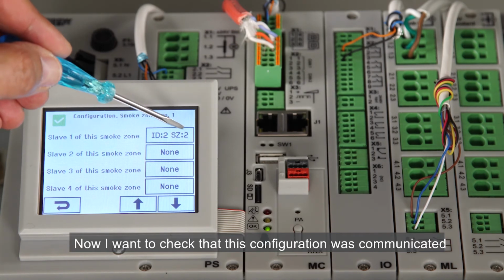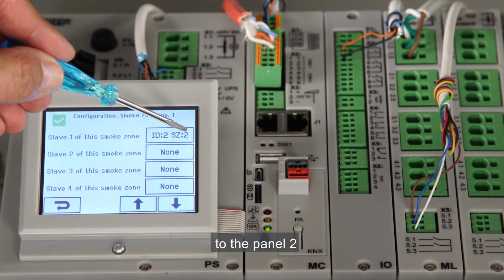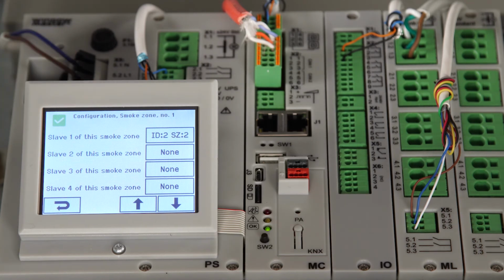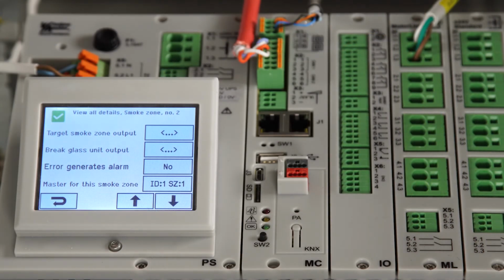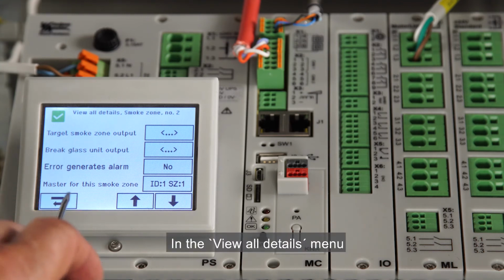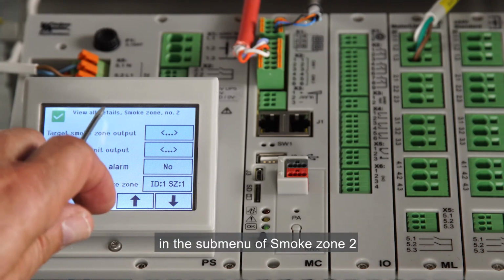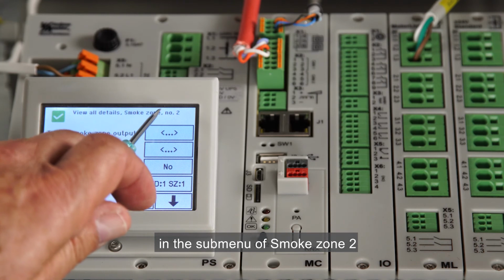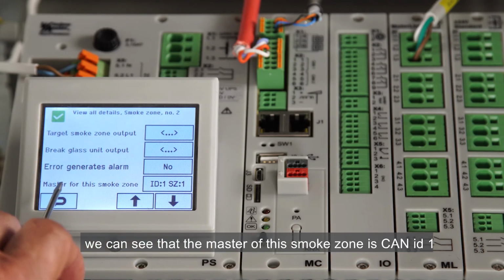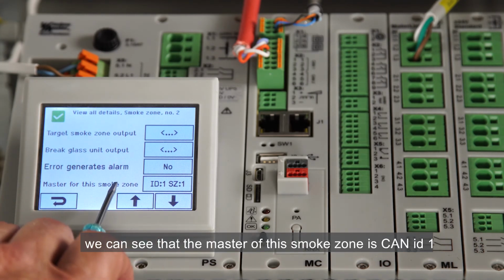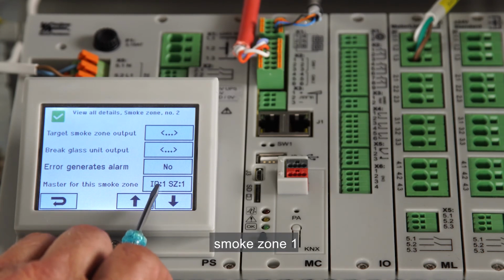Now I want to check that this configuration was communicated to the panel 2. In the View All Details menu in the sub-menu of Smoke Zone 2, we can see that the master of this smoke zone is CAN ID 1, Smoke Zone 1.